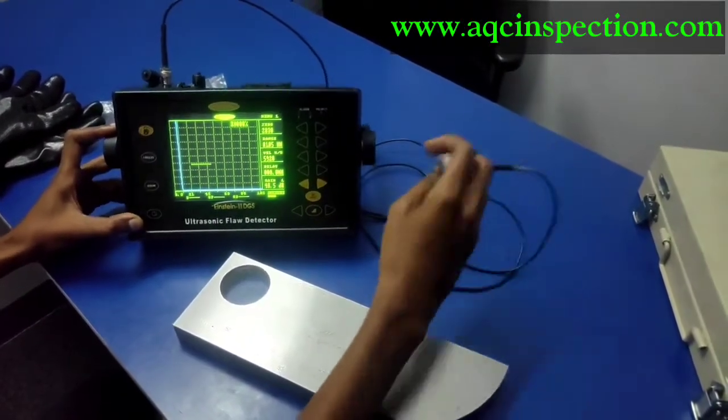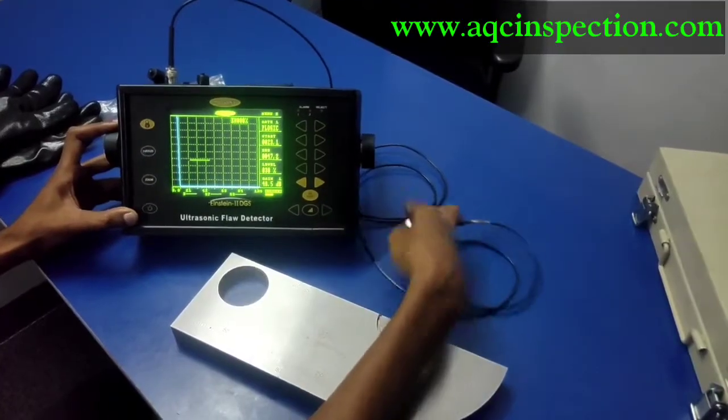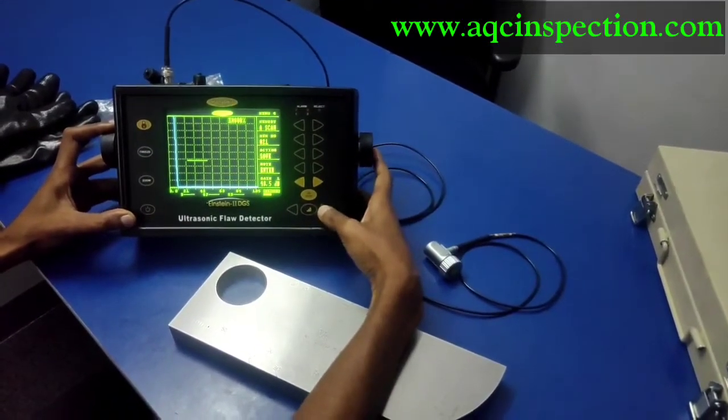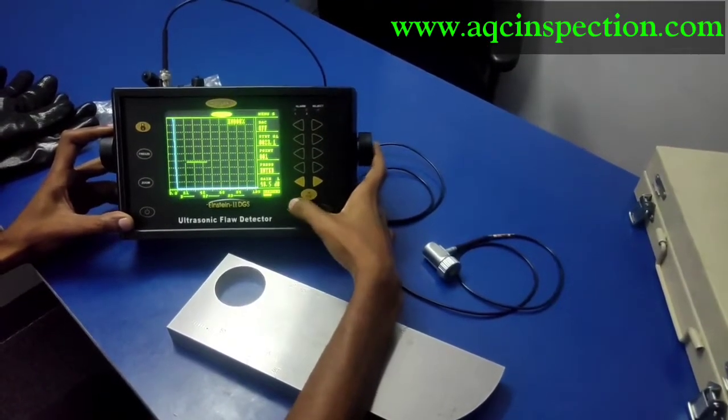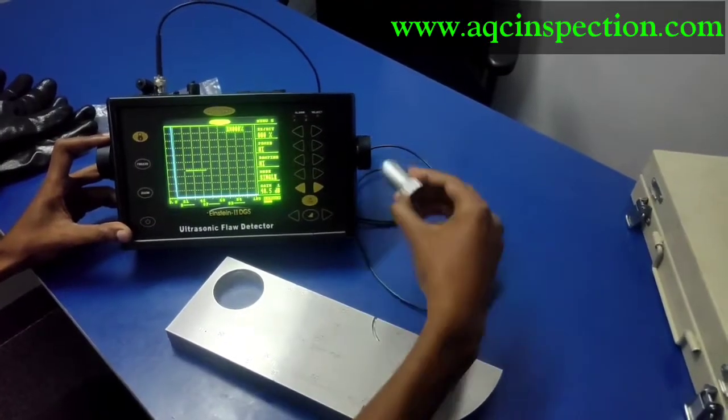So I am going to start calibrating here. Before that, I will set the menus first. If there is anything wrong, we can change it right now. The mode has to be single since it is a single crystal probe.